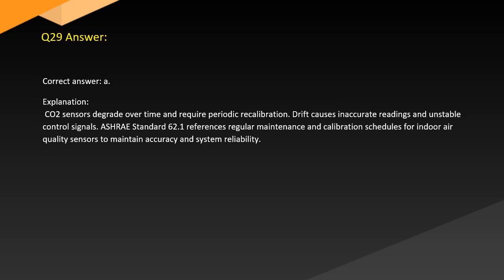Answer. Correct answer: A. Explanation. CO2 sensors degrade over time and require periodic recalibration. Drift causes inaccurate readings and unstable control signals. ASHRAE Standard 62.1 references regular maintenance and calibration schedules for indoor air quality sensors to maintain accuracy and system reliability.